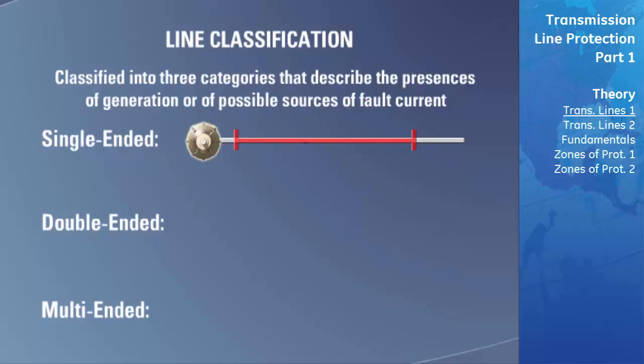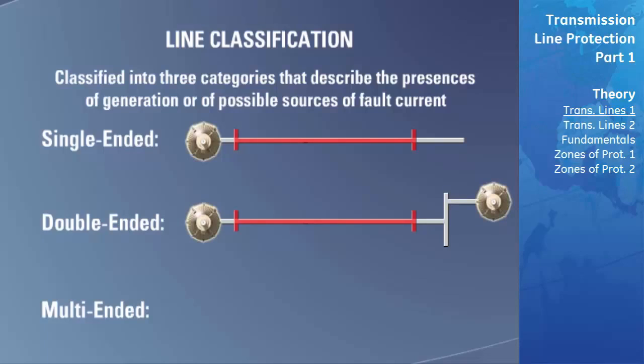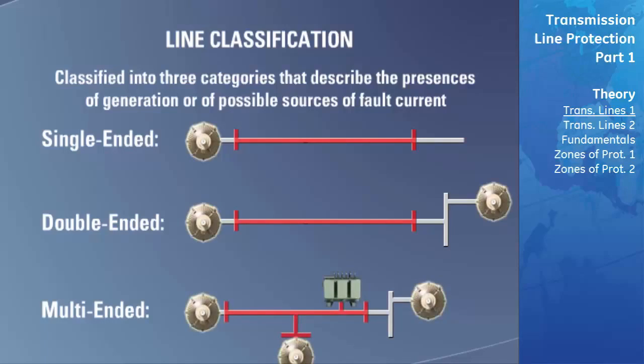A double-ended line has only two boundaries, each of which can have a source of fault current available. This type of line is used to deliver power, usually in different directions at different times. If a fault occurs, current will be fed to the fault from two locations. A multi-ended line has more than two boundaries, each of which can have a source of fault current available. At the time of a fault on this type of line, the direction of normal power flow can be highly variable and the fault will be fed from many different locations.